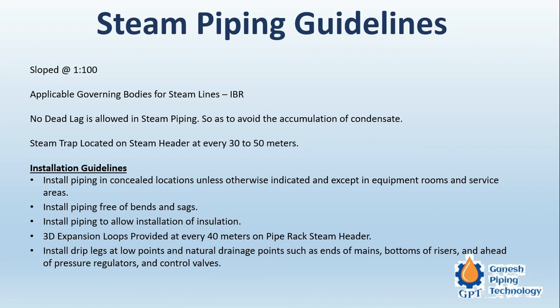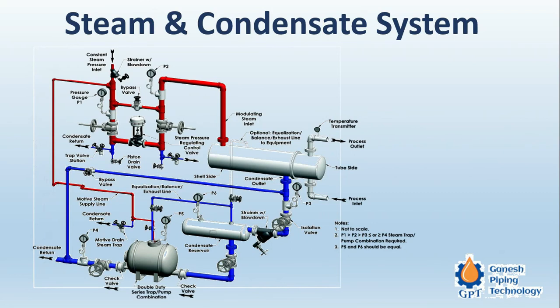Install drip legs at low points and natural drainage points such as ends of mains, bottom of risers, and ahead of pressure regulators and control valves. Control valves are used for stepping down steam pressure. For example, if the main header pressure is 15 bar and different systems require 8 bar, 5 bar, or 10 bar, a control station steps down the pressure. The control valve is set at the required pressure for each system.